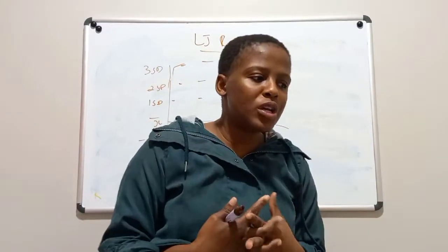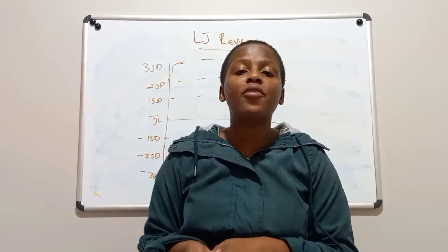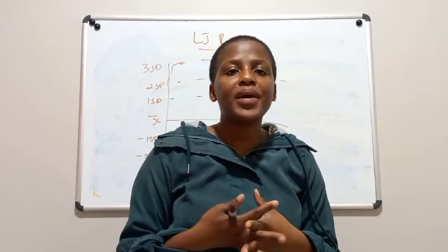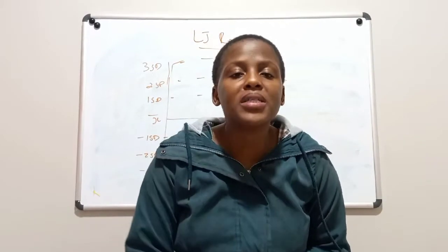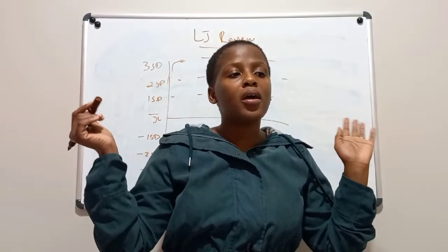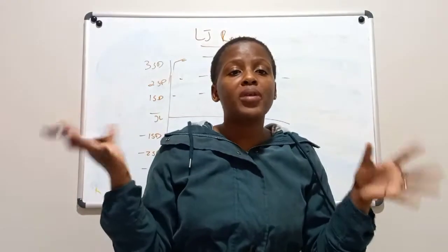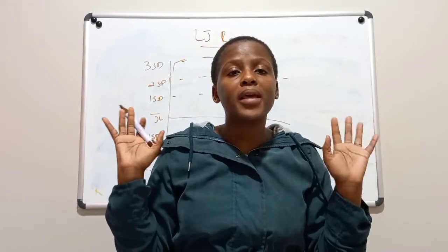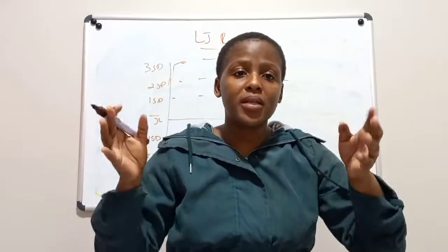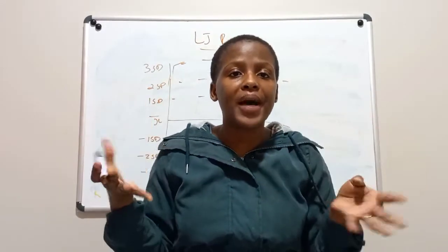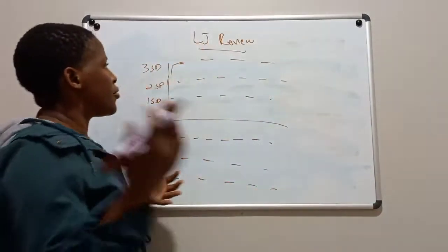So what we usually look for on a daily basis is outliers. Outliers are when the point is outside, depending on the rules of the laboratory. Usually Westgard uses a 3SD range, so we're going to follow that. It means in this case, an outlier will be a point that is outside a 3SD range.